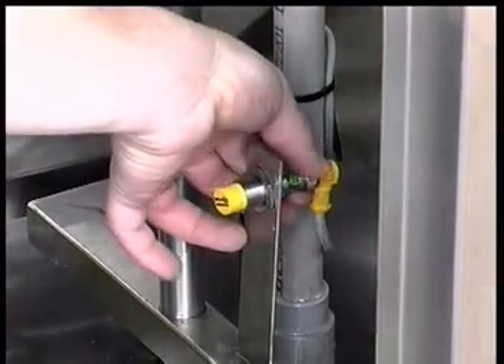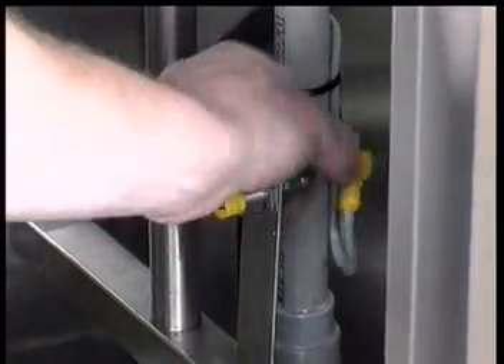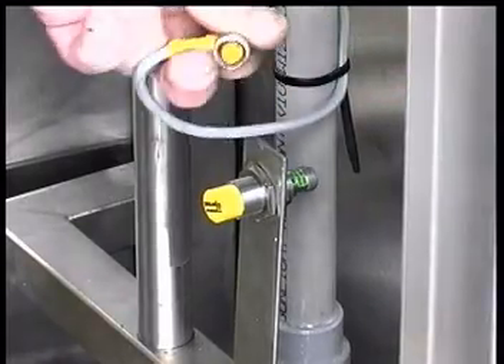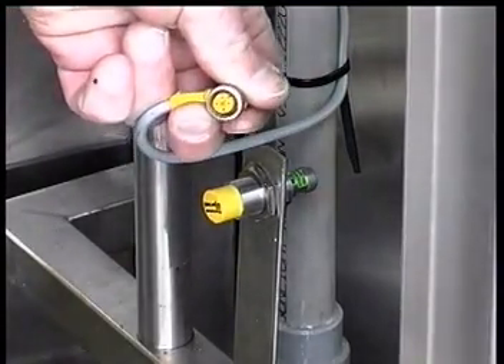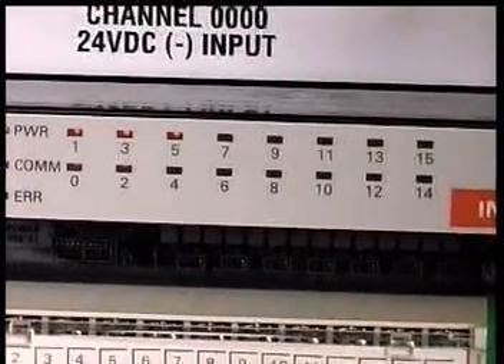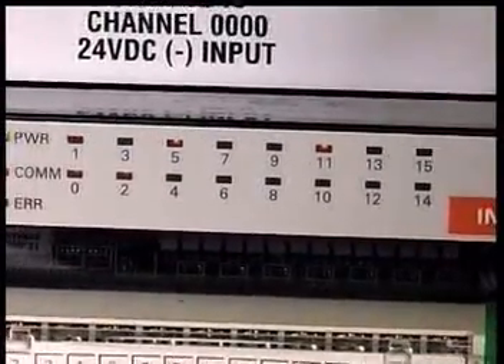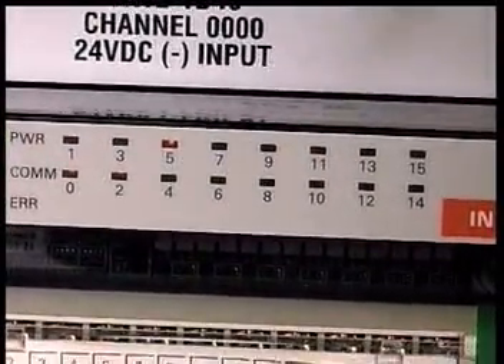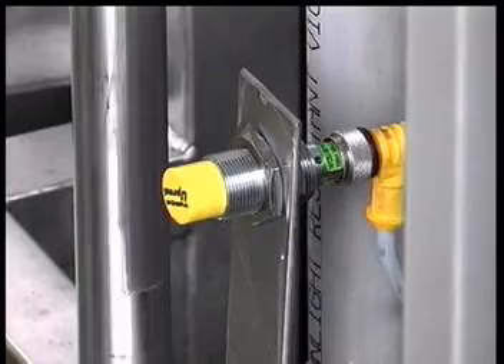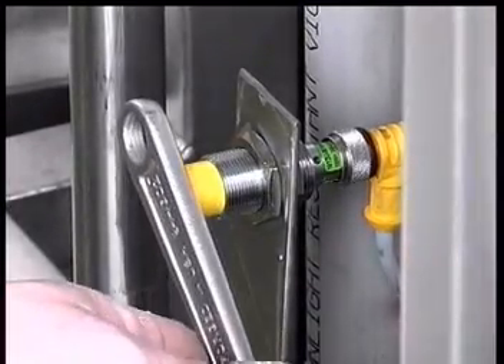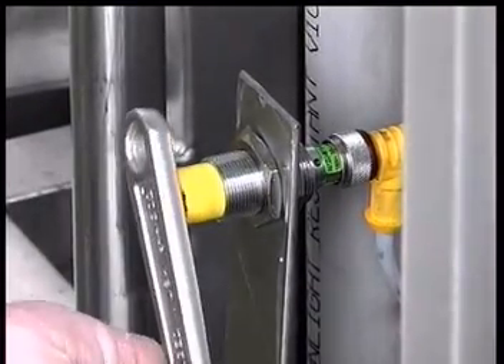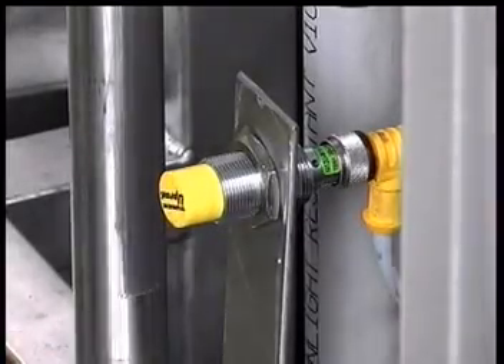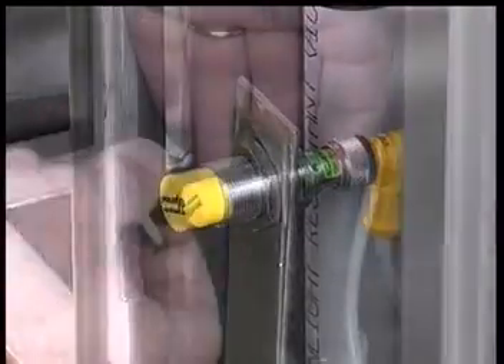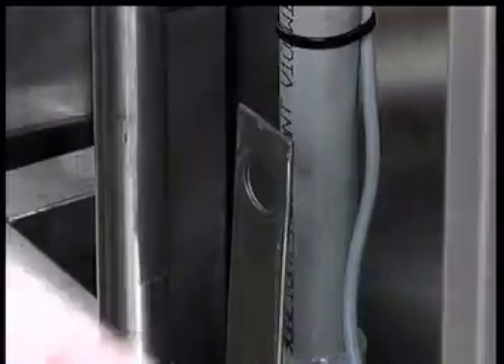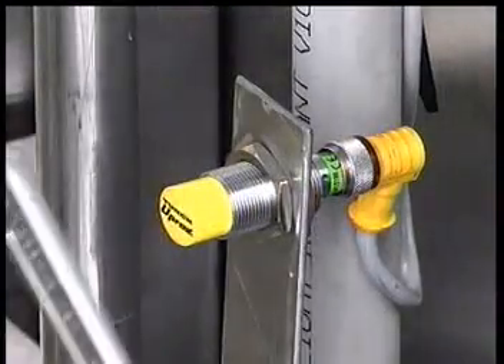The on-off status should change when metal is present and removed. If the light on the prox is on and the on-off status does not change, examine the cable and connections at both ends. The signal is also indicated on the input card in the gantry control panel. The corresponding light should go on and off as the signal changes. If the light on the prox will not light when metal is near, look for loose connections at both ends of the cable and check the cable for breaks. If power and communications are present and cable is okay, replace the prox and retest.